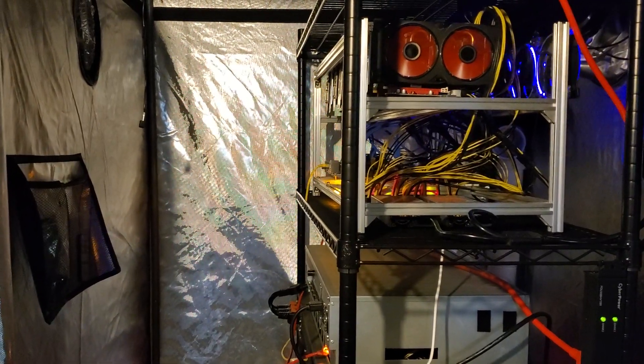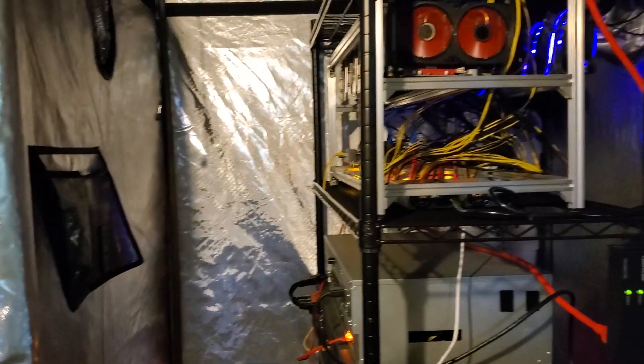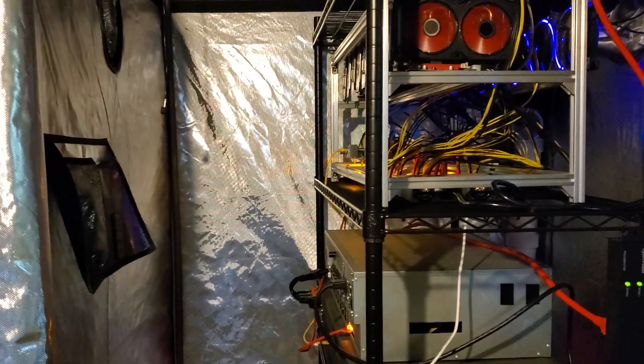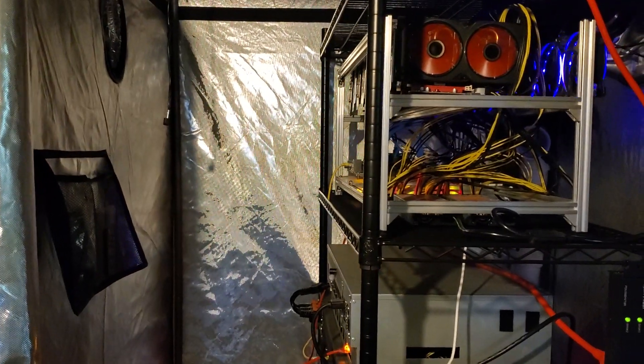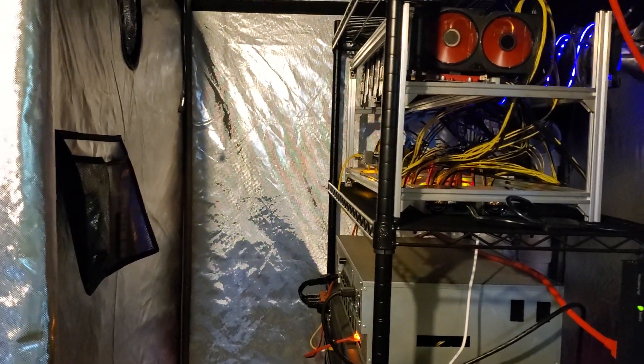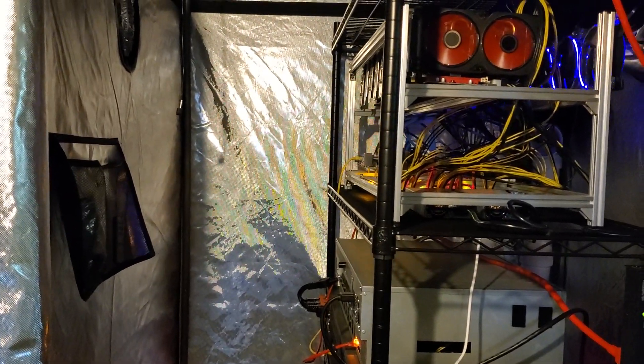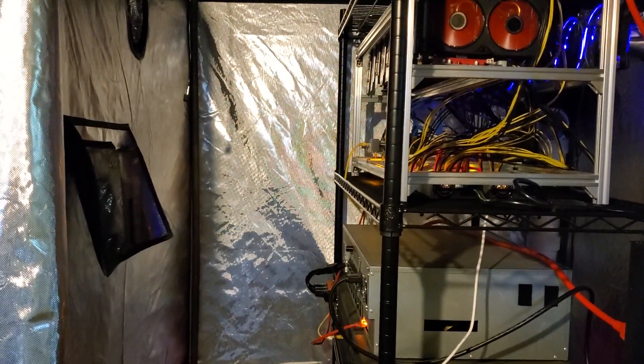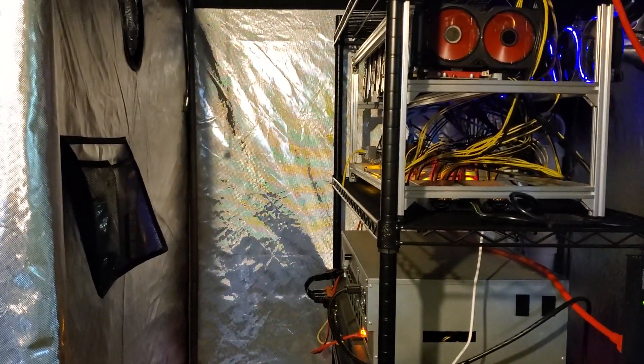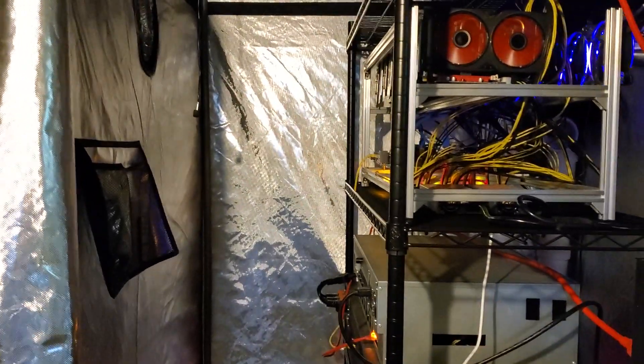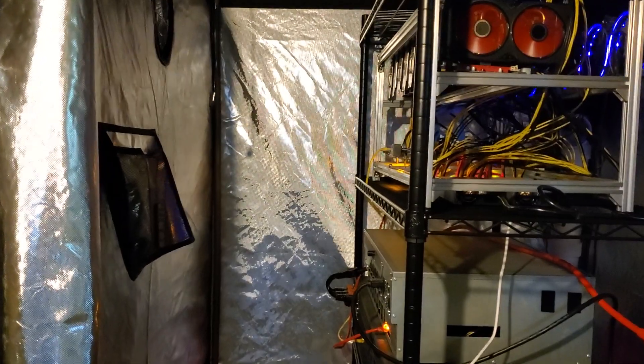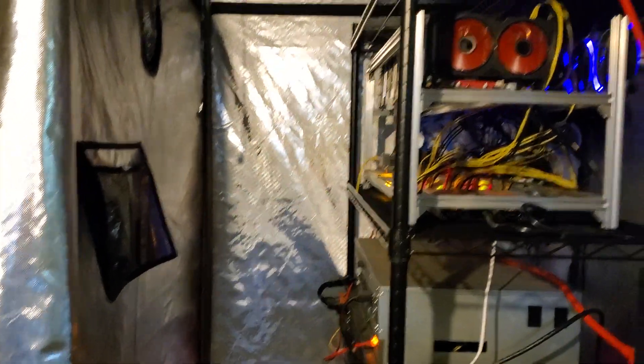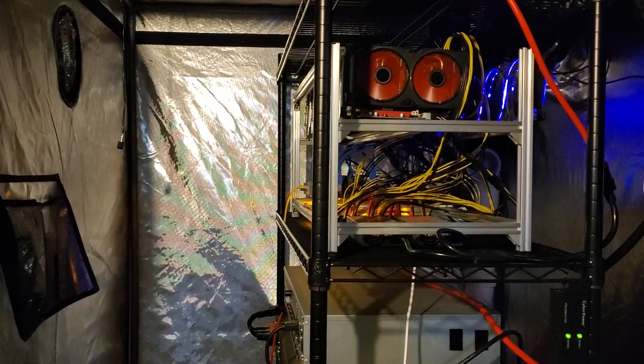In high density air situations, the fan blade is using that to scoop the air and push it across the heat exchangers, which are also reliant on dense air drawing and extracting the heat off the surface area of the heat exchanger, the fins, and removing that heat into the air and then that's getting passed on. So if we're pulling the tent into vacuum, we're actually lowering the air density and making things like fan blades and heat exchangers much less effective.